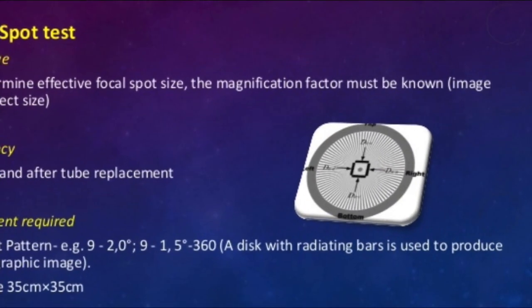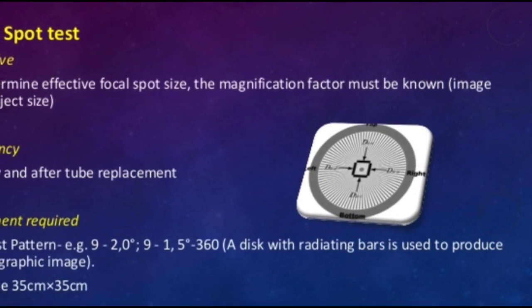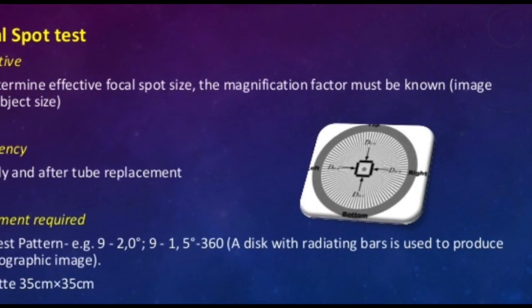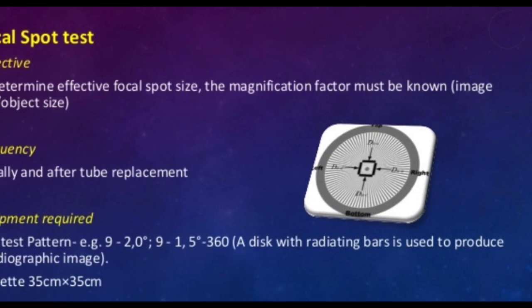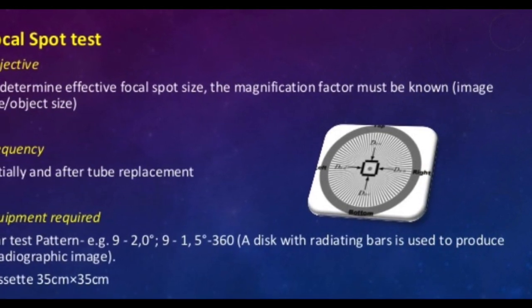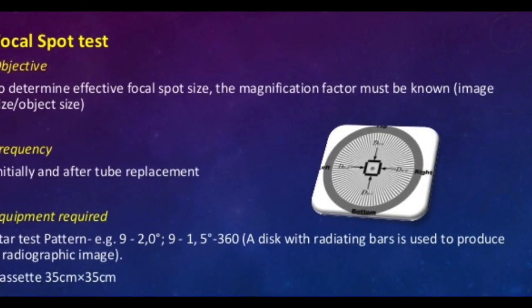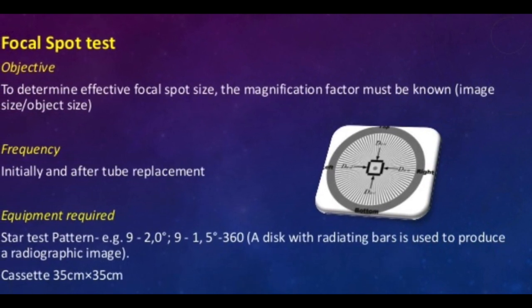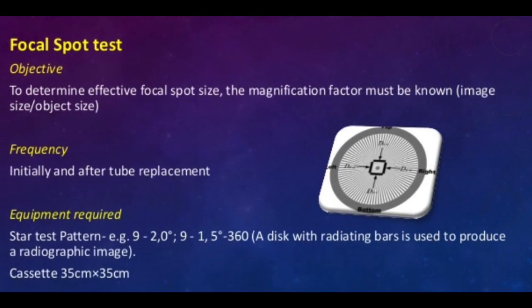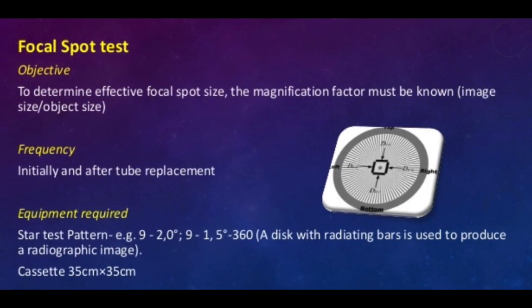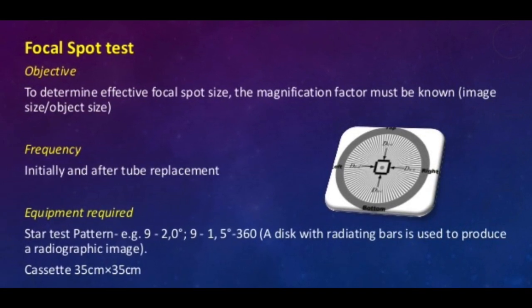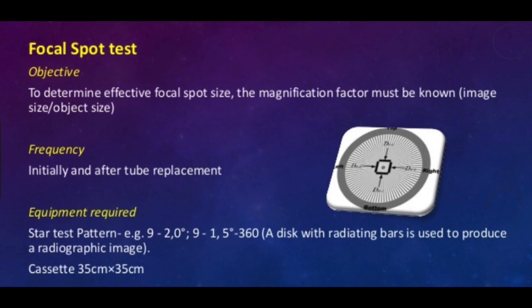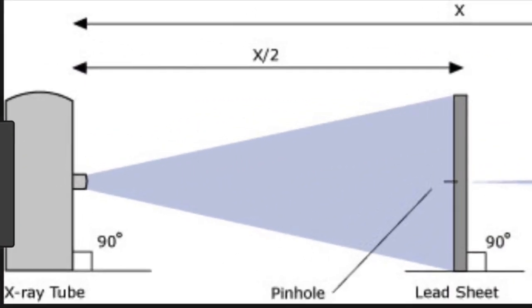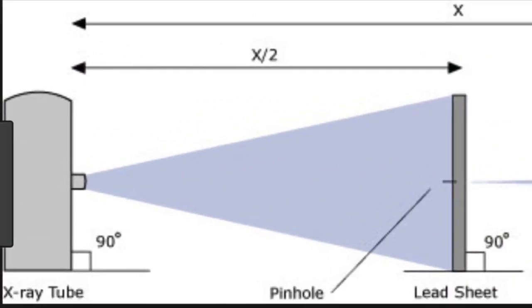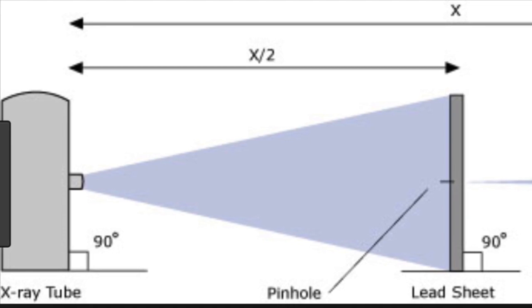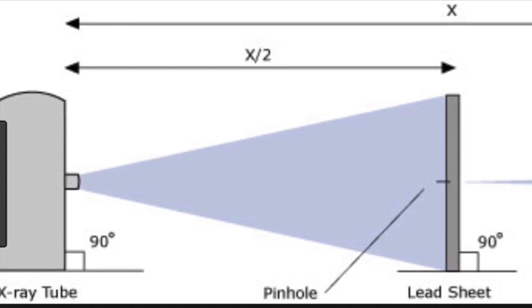Pinhole cameras test the measurement of the focal spot by creating an image of the effective focal spot. Recall that the effective focal spot in relation to the actual focal spot is dependent on the target angle of the anode and the size of the filament. The pinhole camera is not the first choice of tool to use and is reserved for focal spots larger than 1/3 of a millimeter because of its difficulty of use, and user error can lead to inaccuracy of results. In addition, pinhole cameras require excessive tube loading and the resulting heat can damage the tube.